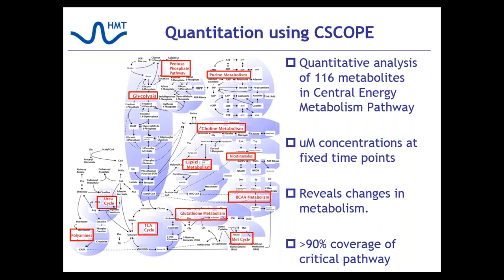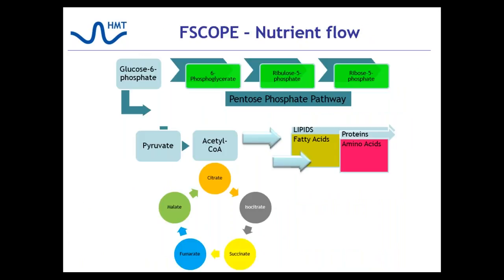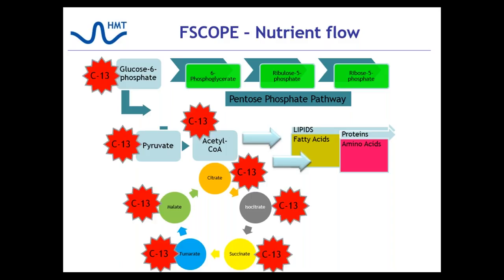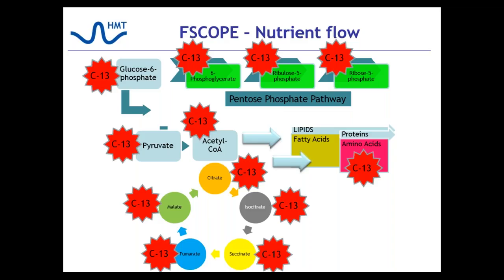C-SCOPE is capable of detecting and measuring over 90% of the metabolites in these energy pathways using the superior selectivity and resolution offered by capillary electrophoresis. F-SCOPE measures a subset of these for isotope analysis. Often Laura will have clients start with C-SCOPE to observe changes in cellular metabolism, then move to F-SCOPE to quantitate and discover the precise movement of nutrients. With unequaled chromatography separation and state-of-the-art mass spectrometry, F-SCOPE can measure isotopomer distribution in over 50 metabolites involved in central energy metabolism, including the TCA cycle, pentose phosphate pathway, and amino acids.